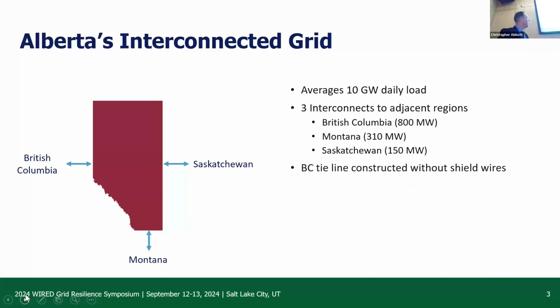What's interesting about them, the BC tie line was constructed and became operational in approximately 1986. It was constructed without shield wires due to cost constraints at the time. Without those shield wires, it's very susceptible to tripping due to lightning strike. Now, Montana is also coupled with that BC intertie via a transfer trip scheme. So if the BC intertie goes out, Montana goes with it, exacerbating the problem.